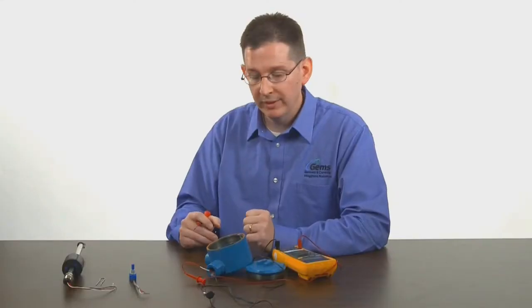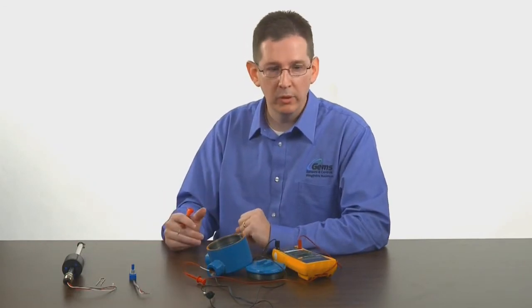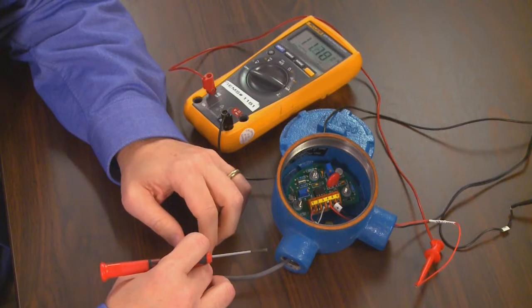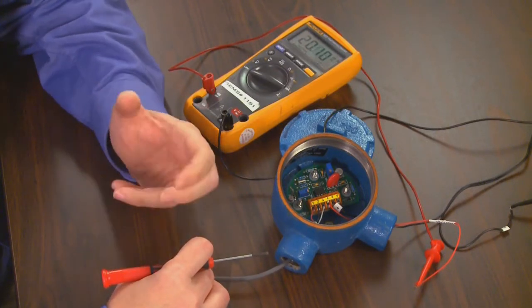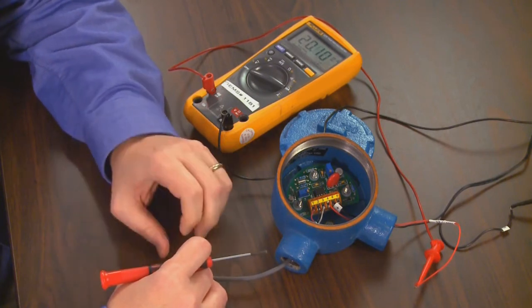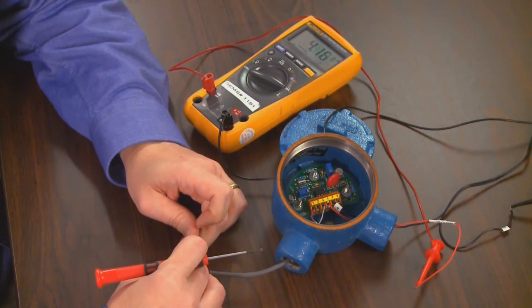Once you have your potentiometer connected, we want to establish the direction of raising and lowering its output. Turning the potentiometer clockwise, you'll notice on the multimeter that the output goes towards 20 milliamps. Counterclockwise, the output drops towards 4 milliamps.